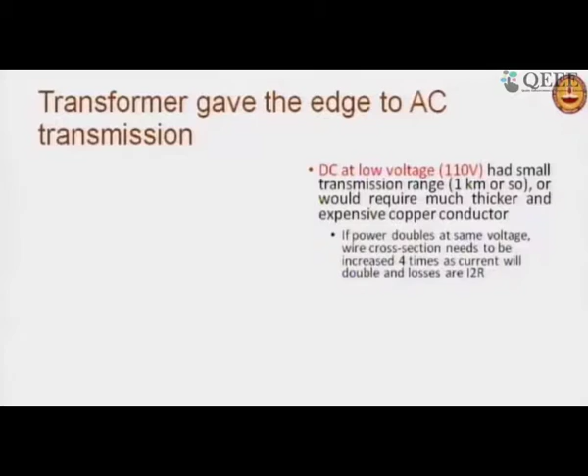In another way, if power doubles at the same voltage, the cross section needs to be increased by 4 times, because the losses are I square R. So essentially, if more power was required, even 1 kilometer range would have been difficult. On the other hand, if I could double the voltage, for the same power, I could go 4 kilometers without much difficulty. So this is where we had a very interesting thing.